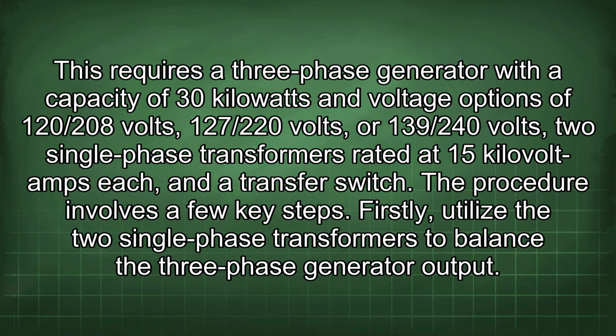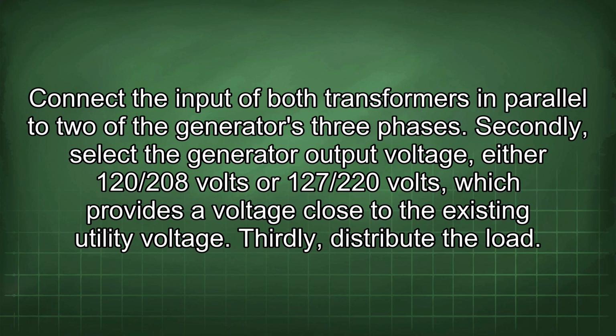The procedure involves a few key steps. Firstly, utilize the two single-phase transformers to balance the three-phase generator output. Connect the input of both transformers in parallel to two of the generator's three phases. Secondly, select the generator output voltage, either 120/208 volts or 127/220 volts, which provides a voltage close to the existing utility voltage.